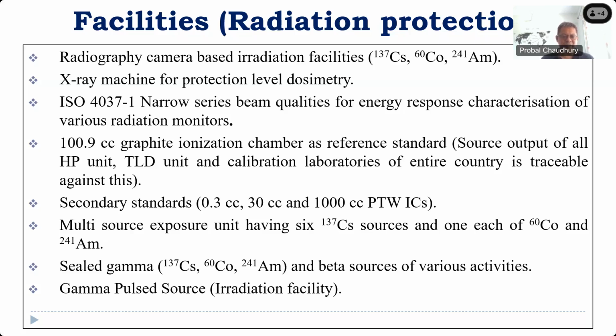Then there is a graphite ionization chamber which is available as a reference standard. This is the reference standard available at protection level for calibration of protection level equipment. The source output of all the health physics units in the country, which are mainly in the reactors and nuclear power plants, is provided traceability using this reference standard. They look after the safety of the working environment as well as personnel. The TLD units and calibration laboratories of the entire country are also traceable against this. So basically, this is the main reference standard used for all measurements for protection level equipment.